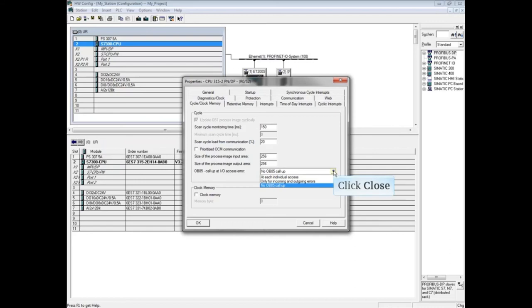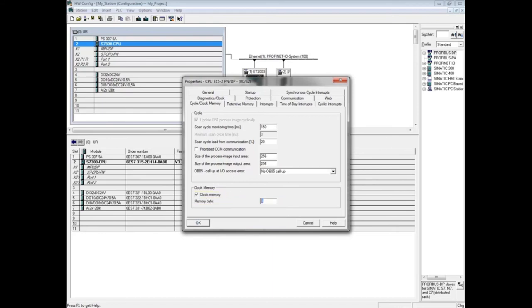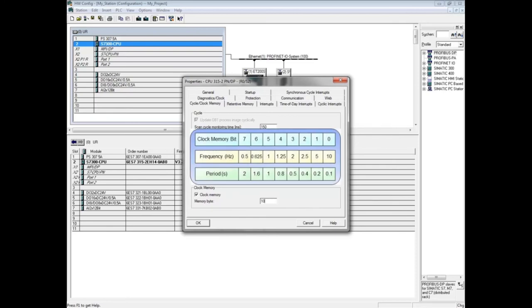The clock memory is the allocation of one byte of the M memory area. Let's assign byte 10. Once a byte is assigned and the hardware configuration downloaded, each bit of the byte begins cycling on and off at specific rates.